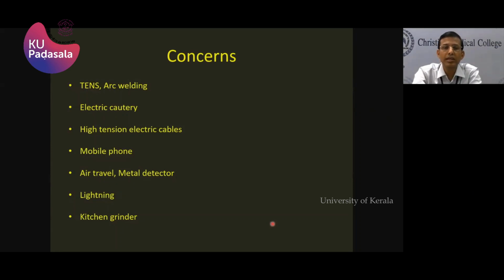Also, when people have a pacemaker and subsequently go in for some other surgery, the surgeons use something called electric cautery to prevent bleeding. This electric cautery cannot be used if you had a pacemaker implantation. However, there are different types of electric cautery. There's bipolar and unipolar, and it is advisable to use a bipolar cautery rather than a unipolar cautery. And again, if the area of surgery is more than 6 inches away from where the device is located, then it may be safe to use a bipolar electric cautery.